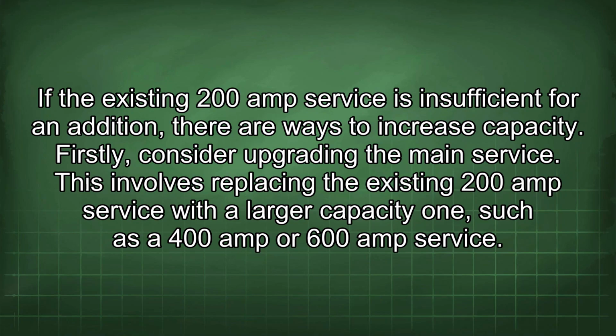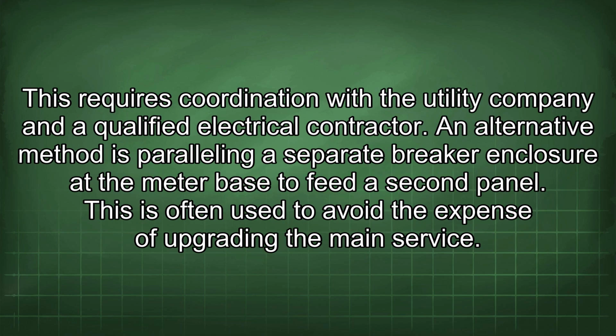If the existing 200 amp service is insufficient for an addition, there are ways to increase capacity. Firstly, consider upgrading the main service. This involves replacing the existing 200 amp service with a larger capacity one, such as a 400 amp or 600 amp service. This requires coordination with the utility company and a qualified electrical contractor.